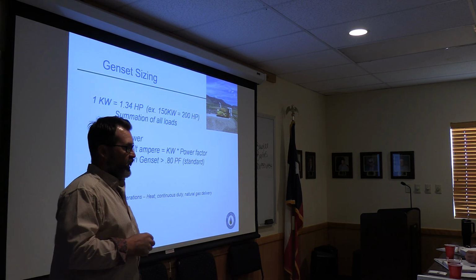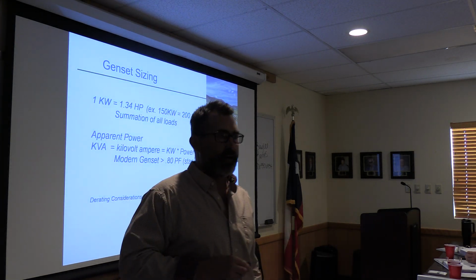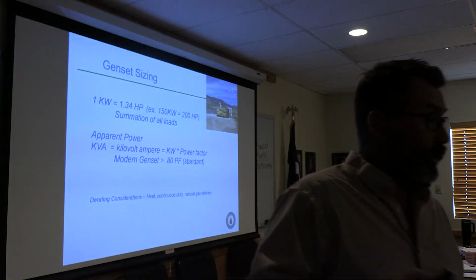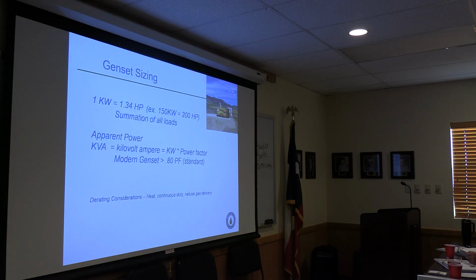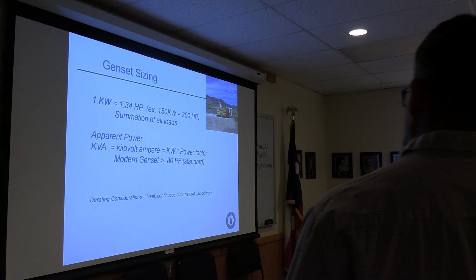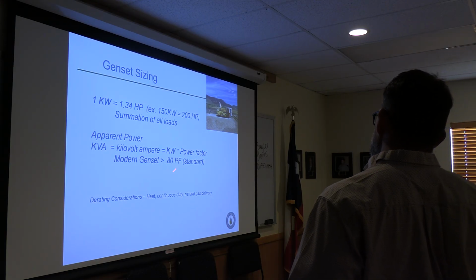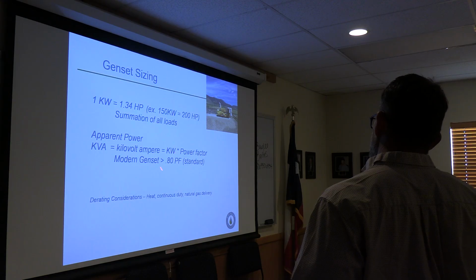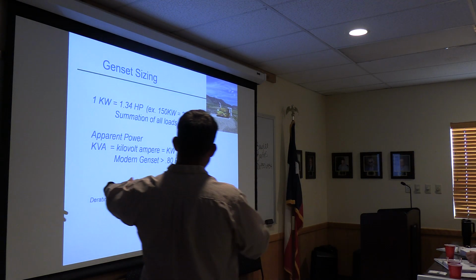0.8 is what's on the label. Most of them will outperform that, something like 0.87 to 0.9. It's really good power. Don't get me wrong, grid power is often off by a factor more than that, but because this is a bit of a derate, every bit of power factor that's less than 1 is actually less power you can deliver to your wells. So it's something you've got to be mindful of.